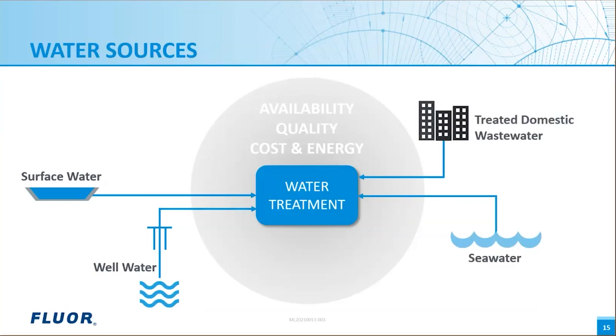Treated domestic wastewater is now routinely being considered as a source of water. This water is comparable to freshwater sources in many regards, but contains enough salts to require additional treatment, such as ultrafiltration or reverse osmosis. In some cases, it can be used directly for cooling water makeup. In most locations, this water is readily available. However, it could become more scarce in the future as demand increases.